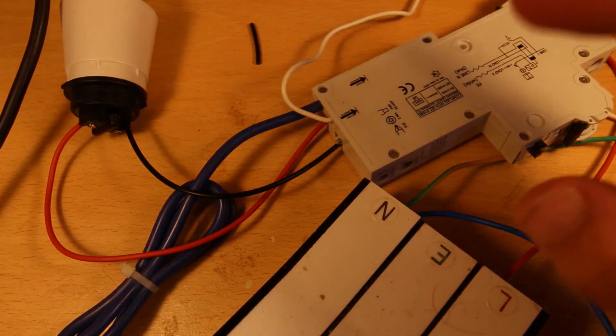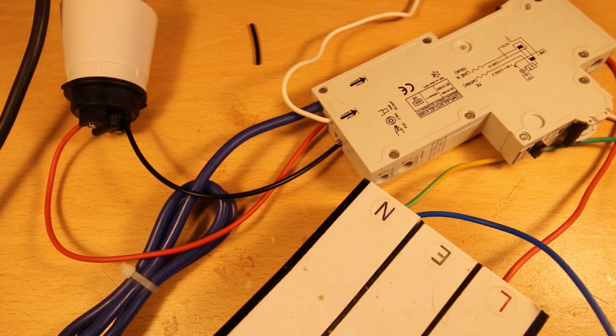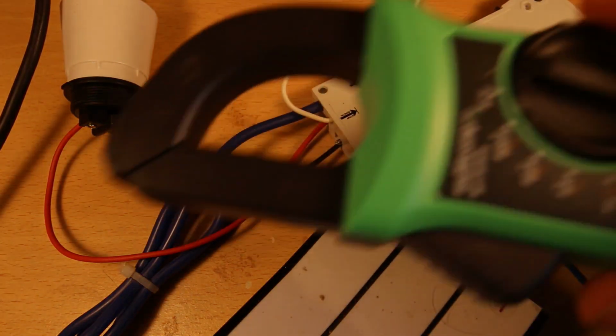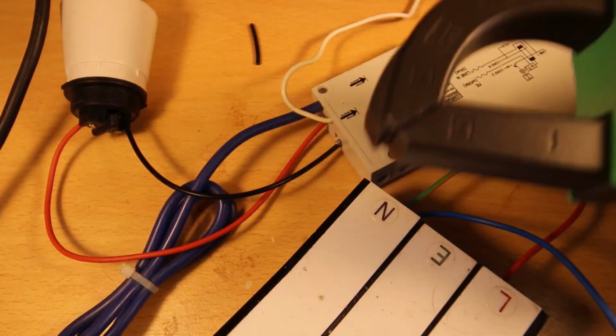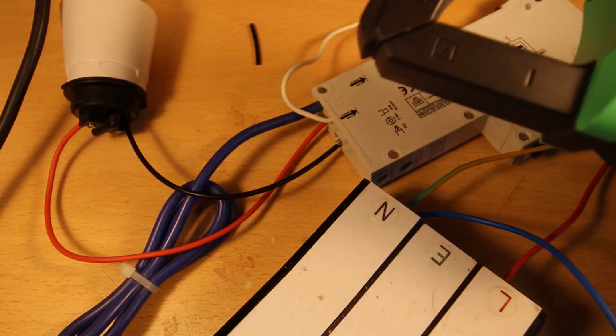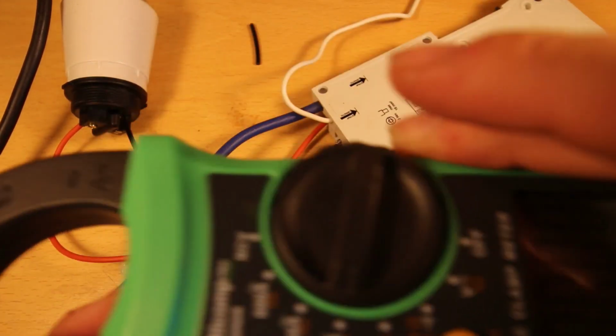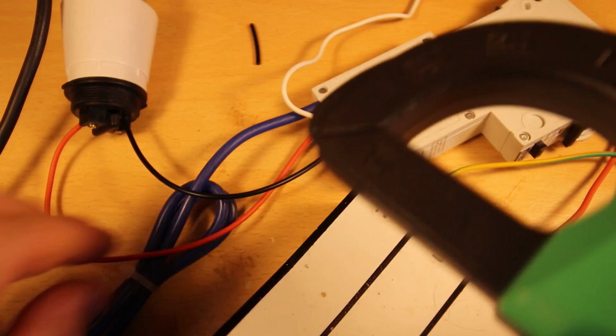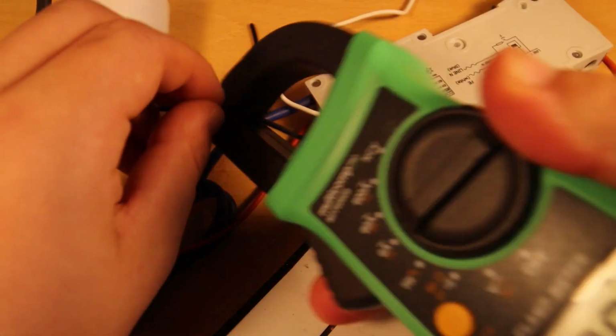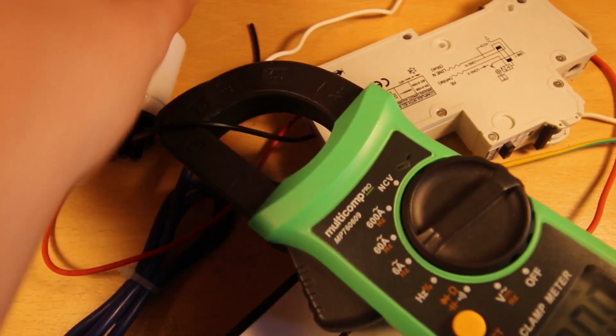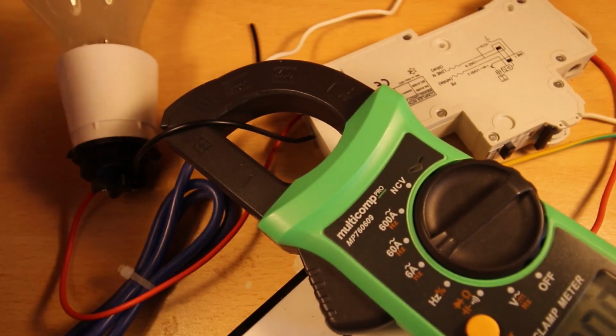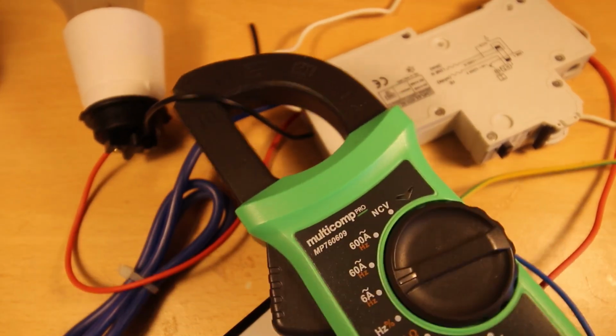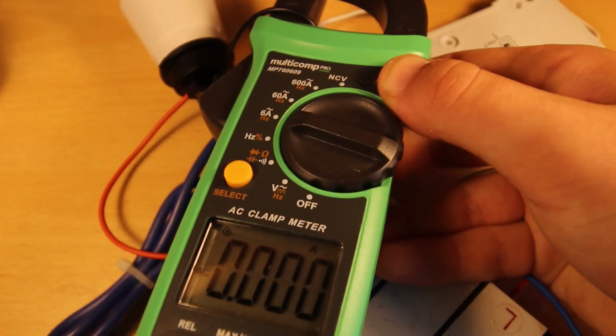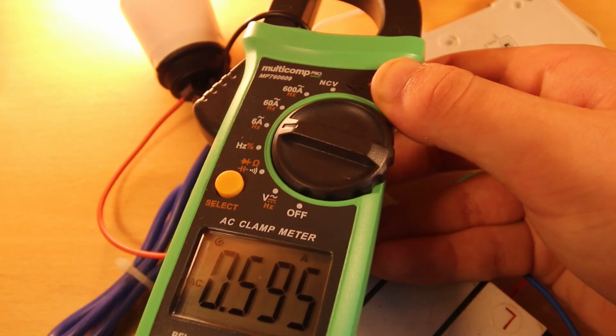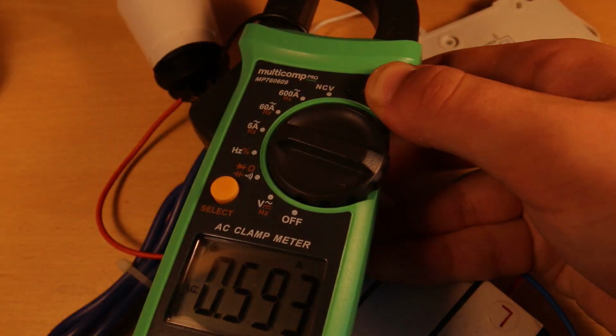So we have the same setup as before, essentially. What I've got now is my current clamp meter, so I can show you the leakage that is being measured by the RCD. If I set this to 6 amps non-contact current, and I put that around just one of the terminals. What's that light bulb touching? It's not going to burn anything. Good. This is awkward because I need to show you the screen. There we go. If I then turn this on, you can see we have just under 600 milliamps flowing.